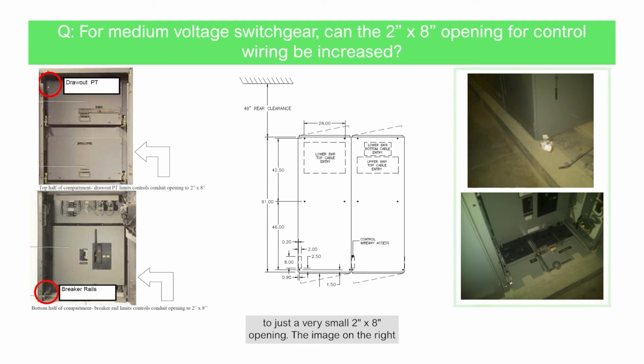The image on the right shows what a common installation technique is with the medium voltage gear. When you have this switchgear pad, there's oftentimes a trench that's about 2 by 8 inches or a little bit larger, just where it's going to line up with that opening for the control wires, so that the contractor can bring all the control wires into that larger trench that runs the entire width of this switchgear and then be able to route the wires up through the 2 by 8 inches opening in lieu of having to make sure that he aligns the conduit directly to that opening on the bottom of the switchgear.